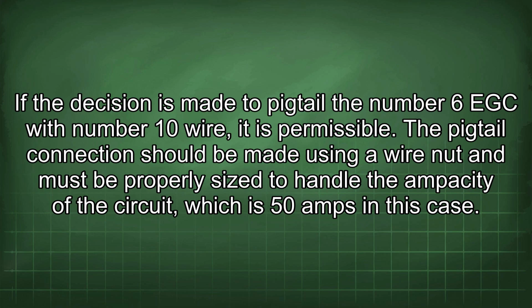If the decision is made to pigtail the number 6 EGC with number 10 wire, it is permissible. The pigtail connection should be made using a wire nut and must be properly sized to handle the ampacity of the circuit, which is 50 amps in this case.